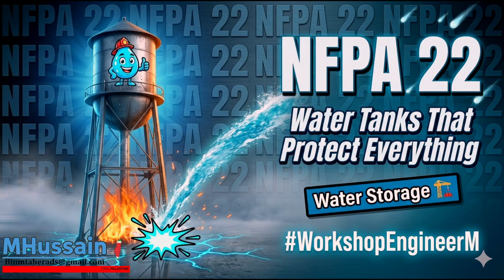If you install an FRP tank inside a building, the standard mandates it must be protected by automatic sprinklers, specifically engineered to ordinary hazard group 2, or OH2, requirements. The challenge with FRP is the chemical composition of the resins used to bind the fiberglass. Unlike steel or concrete, which are non-combustible, many FRP resins will burn. Even the fire retardant ones.